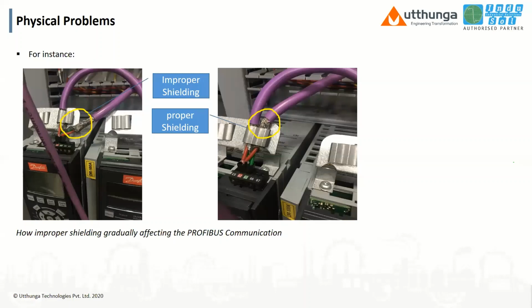So here I'm going to explain some real-time scenarios and real-time issues that we found when I visited a lot of plants and did service measurements. In the left side image, you can see the shielding was not as recommended. After the service measurement, we made the shielding proper. What happens if shielding is not done properly? Grounding will not work properly, right? Then the communication will get affected gradually. This will cause intermittent failures, and the communication voltage will also get affected.